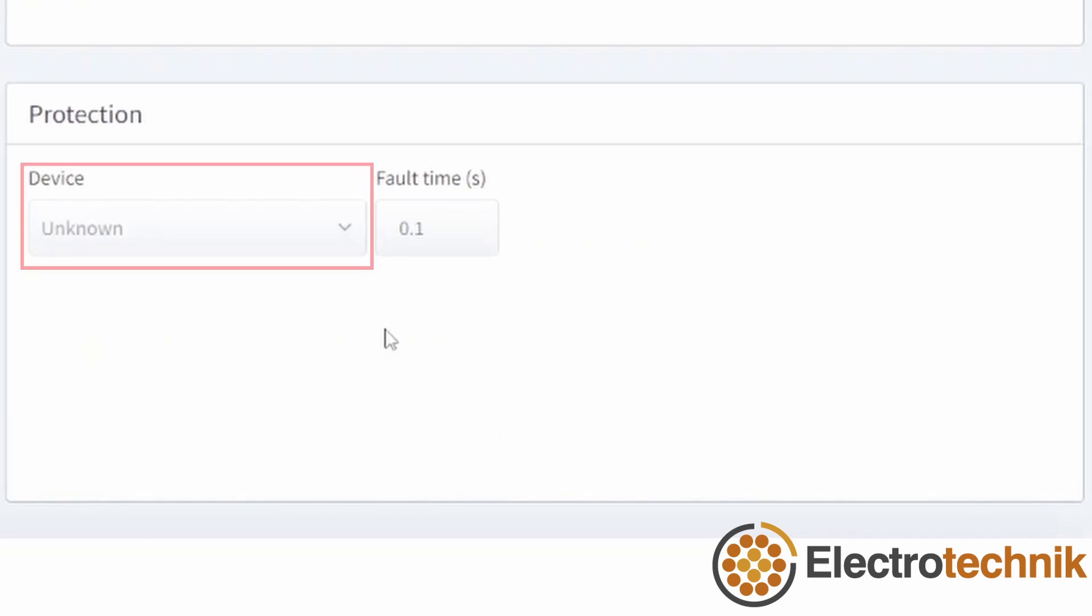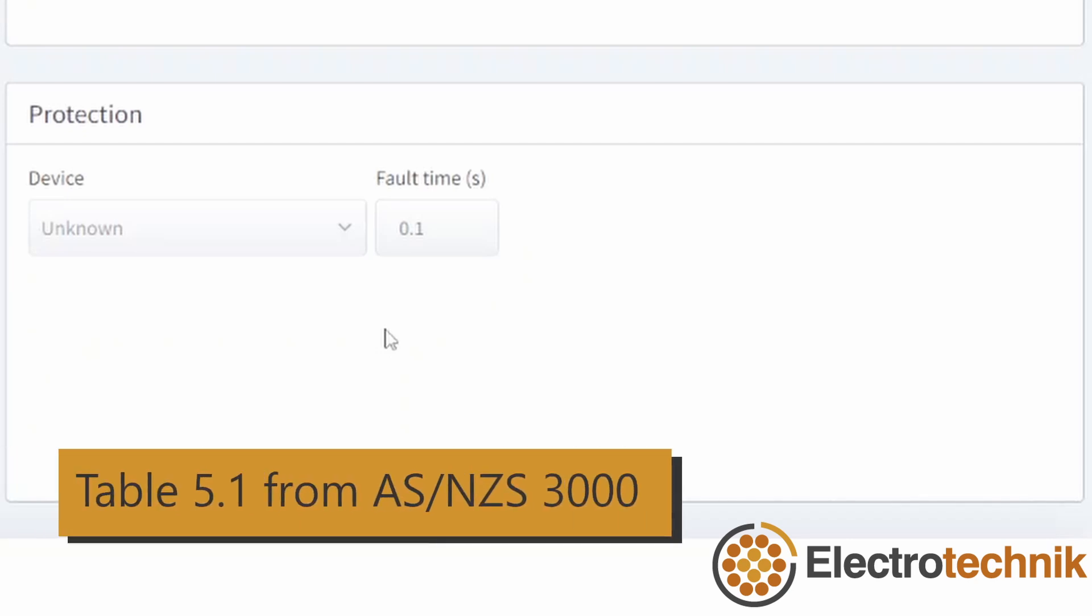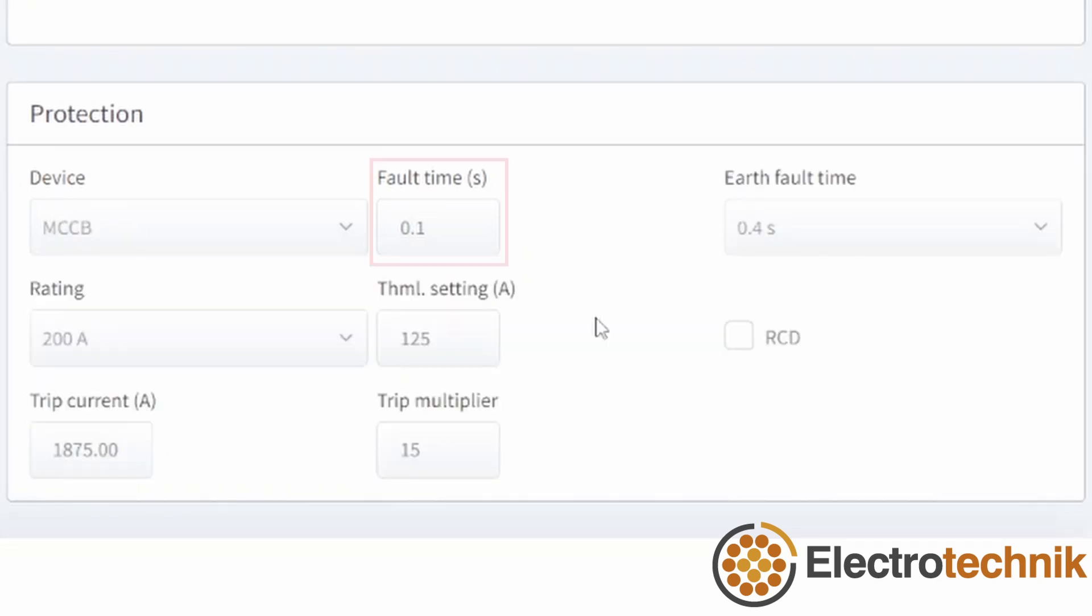Note that if the protective device is unknown, then the earth cable size will be based on table 5.1 from AS-NZS 3000. Otherwise, earth size will be based on fault loop impedance from the protective device settings.